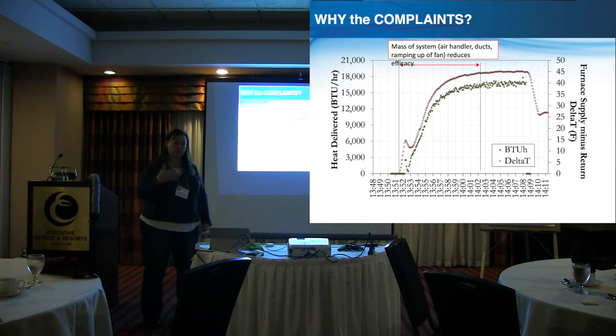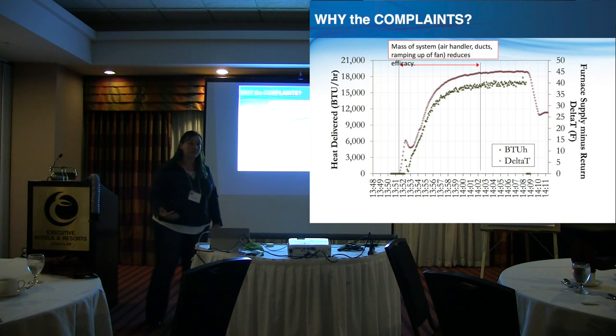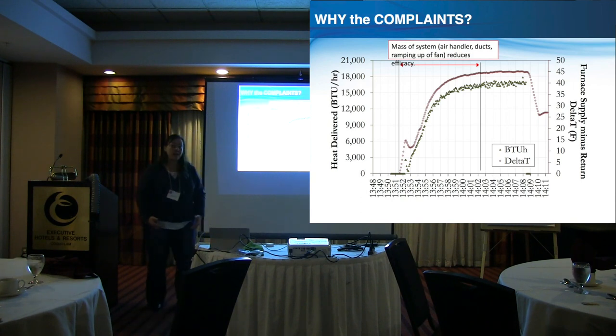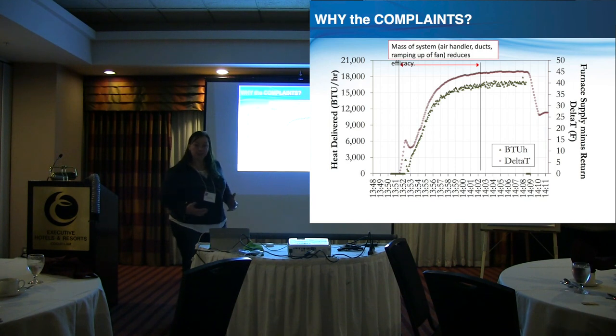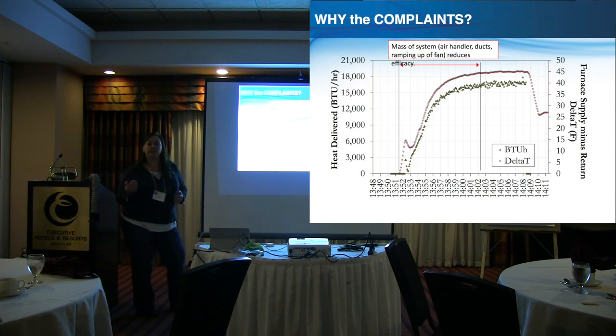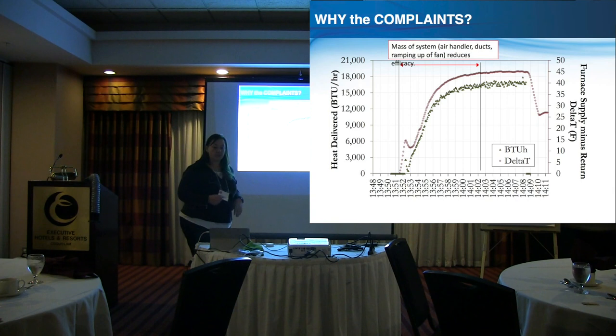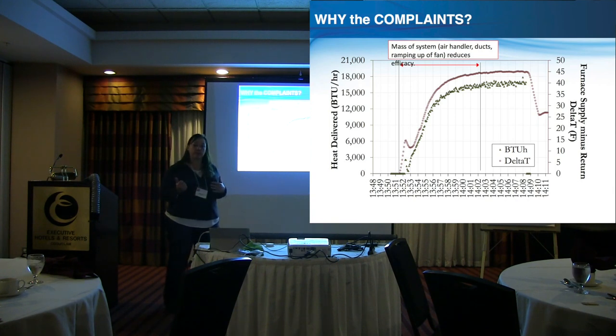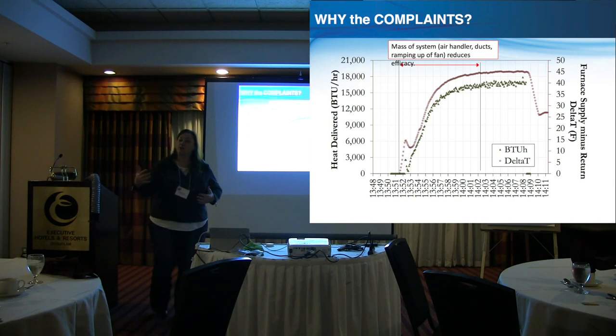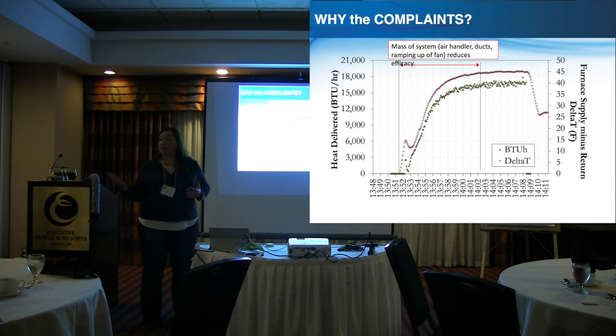So backing up to 2008, 2009, when Energy Star for New Home Builders were calling me saying, we've got a problem. We're building houses better than we ever have before. Why are we getting more and more comfort complaints? We're constantly in those houses because the homeowners aren't comfortable. So we're building houses better. What is the problem? So in labs, we were able to identify what the problems were. So we have overshooting and short cycling, primarily as a result of oversizing equipment. So in our lab tests, in a high performance home, it took 14 minutes to hit the delta T between conditioning the space, between the main plenum of the furnace to the last room in the house. So when we're short cycling 10, 12 minutes, that's why that last room in the house is not getting treated properly.